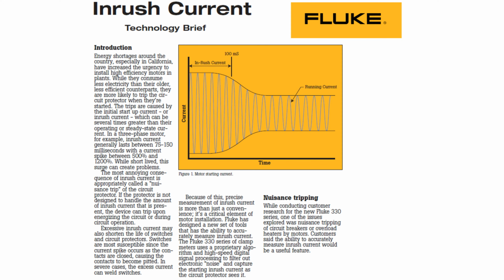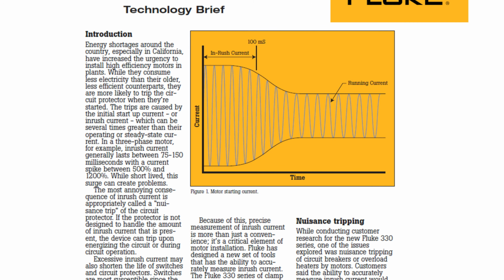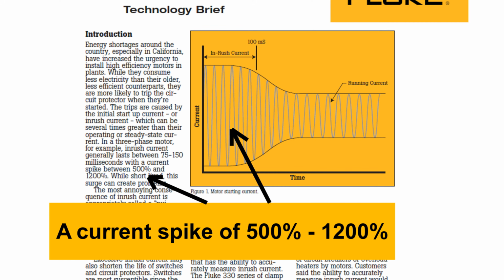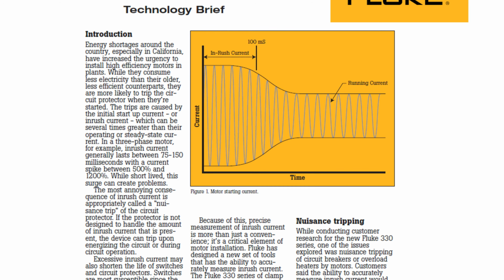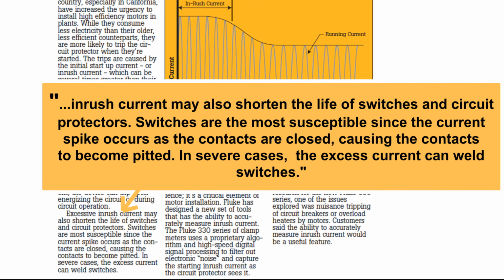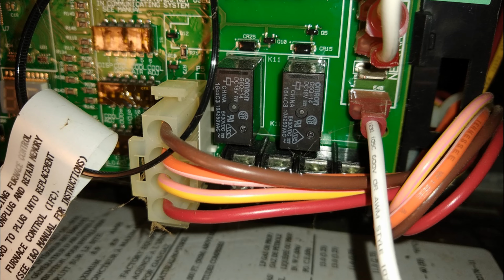Motor power circuits are usually designed to deal with the special problems of motors. For one thing, when a motor starts up, it draws anywhere from 3 to 5 to even 10 times its normal operating amperage for 0.2 of a second or even more. Then when it shuts off, there's a bigger challenge for the relay contacts. Trying to open up under spring pressure, the contacts draw an arc between them until they're far enough apart to stop the current from jumping across. This causes pitting of the contacts over time until they're too burned out to work without heating up. Mind you, that excess heat would be generated on the control board.